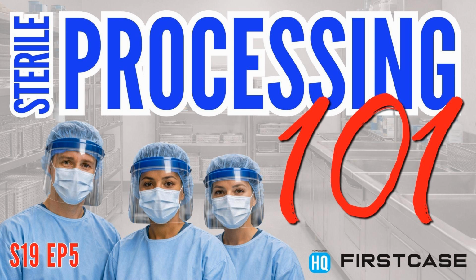If you're working in a research facility, you might find some other peculiar ones, like an ozone sterilizer. Yeah, I've heard of that one. If you worked in maybe a dental facility, you might have a little tabletop sterilizer, and that could work either by creating its own steam, a little steam autoclave, or there are some that just operate by dry heat, like your oven at home. You just cook it at a really high temperature for a really long period of time. So those are all the main strategies we have: steam, dry heat, and different forms of low temperature chemical sterilization. So then let's look at steam, because steam is the lion's share of what we do.